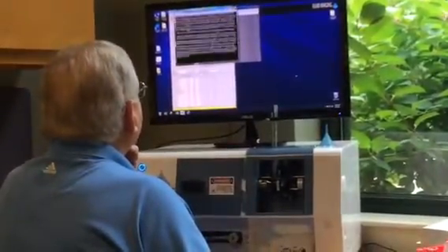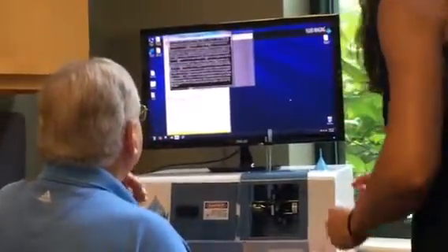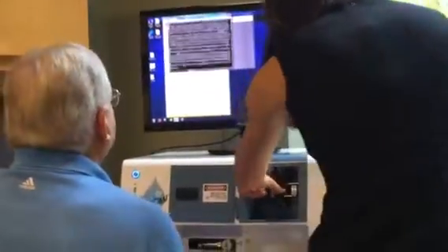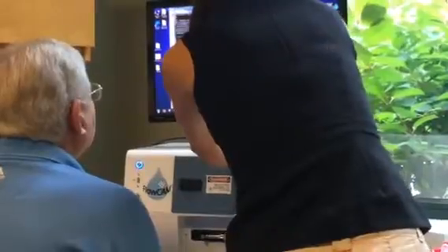Settling. Oh, looks like this was knocked out of focus. I think the janitor was in here yesterday, he might have moved the instrument. You just have to remember that. And you don't have to stop the run to focus it, you can just do it mid-run. And look how much better off we are now, getting one particle per image, so we're getting much better data, much more reliable counting.